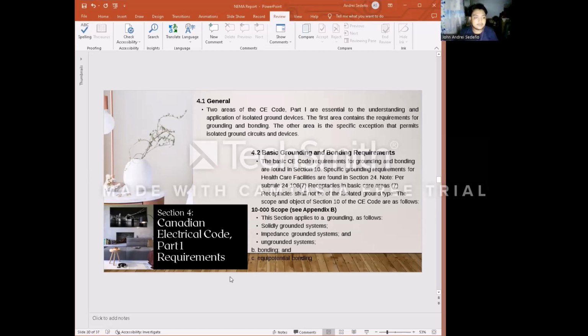Now, we're going to tackle the Canadian Electrical Code Part 1 requirements. In general, two areas of the CE Code Part 1 are essential to understanding the application of isolated ground devices. The first area contains requirements for grounding and bonding. The other area is a specific exception that permits isolated ground devices.